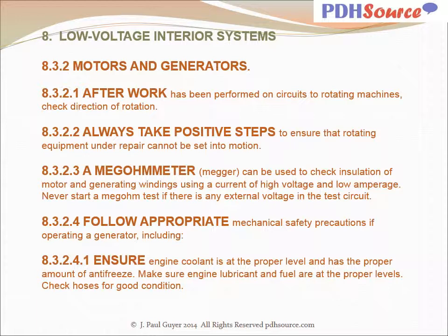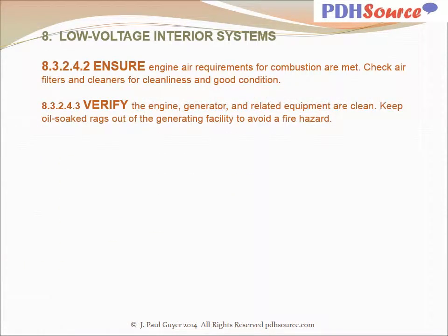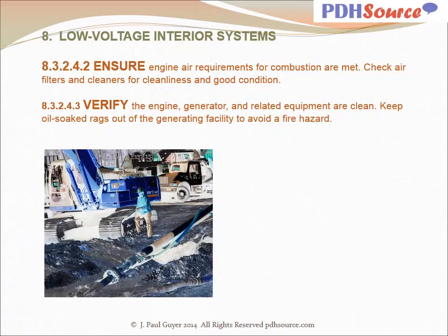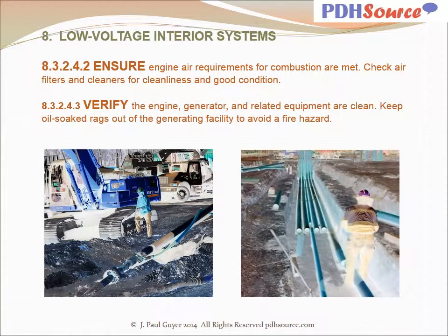Follow appropriate mechanical safety precautions if operating a generator, including ensure that the engine coolant is at the proper level and has the proper amount of antifreeze. Make sure engine lubricant and fuel are at their proper levels. Check hoses for good condition. Ensure that engine air requirements for combustion are met. Check air filters and cleaners for cleanliness and good condition. Verify the engine generator and related equipment are clean. Keep oil-soaked rags out of the generating facility to avoid a fire hazard.